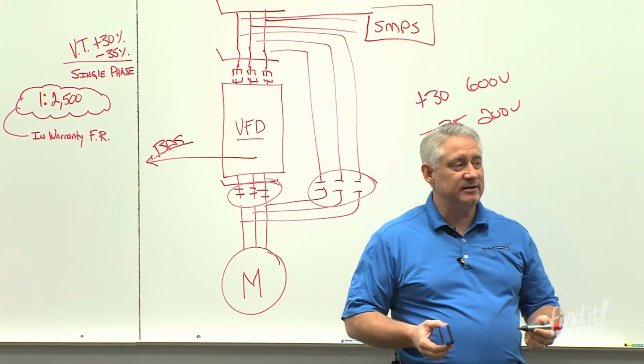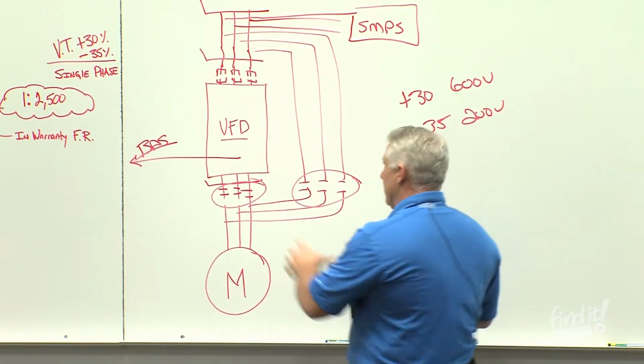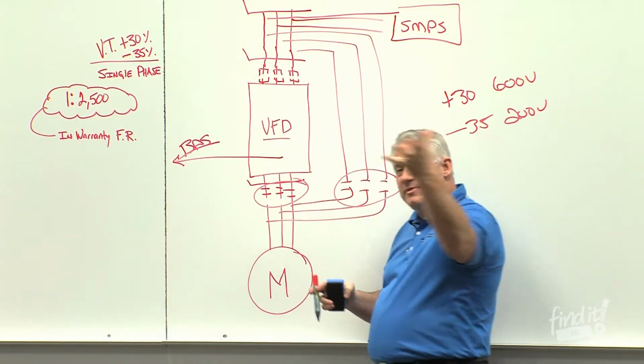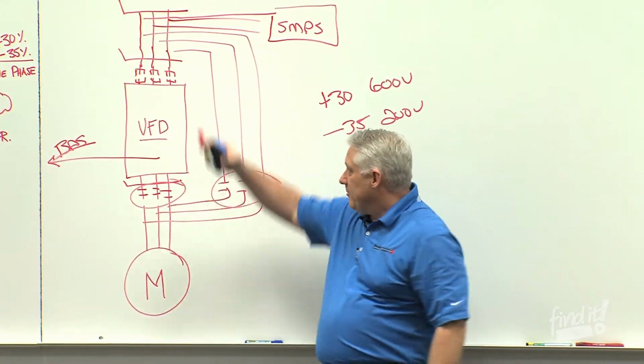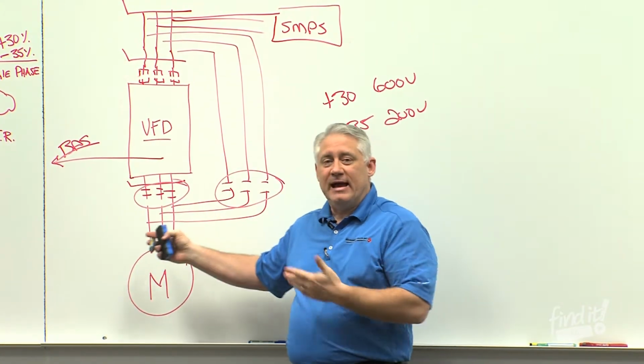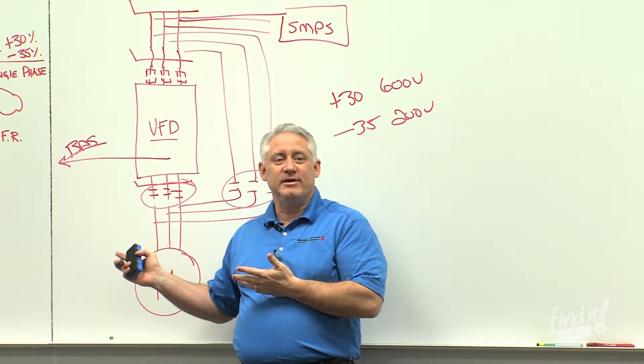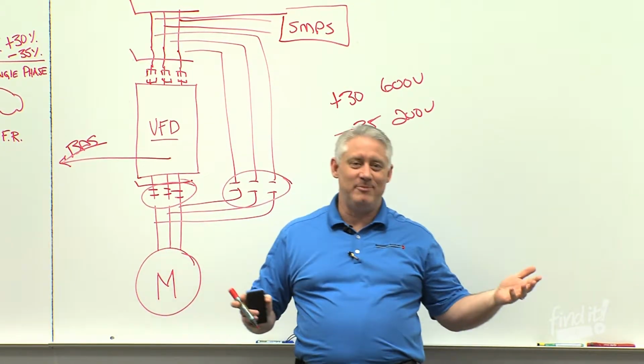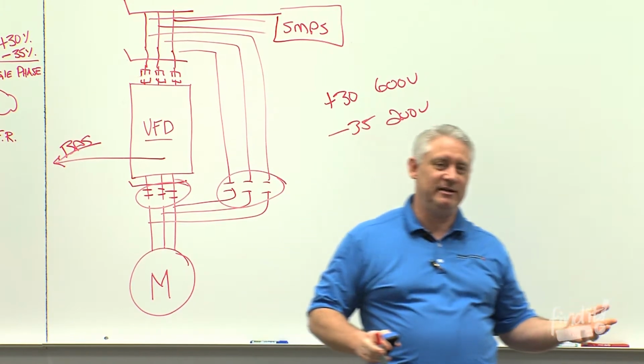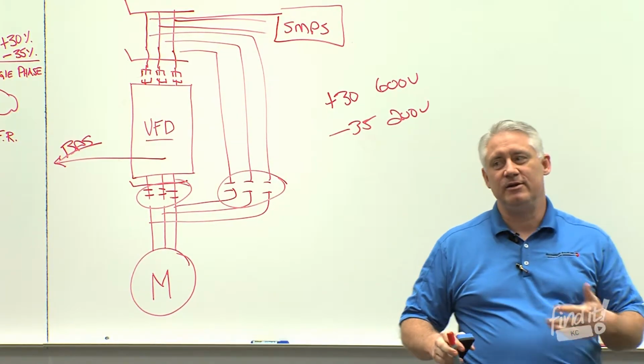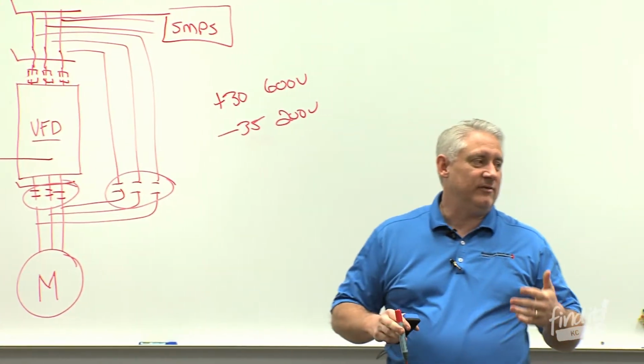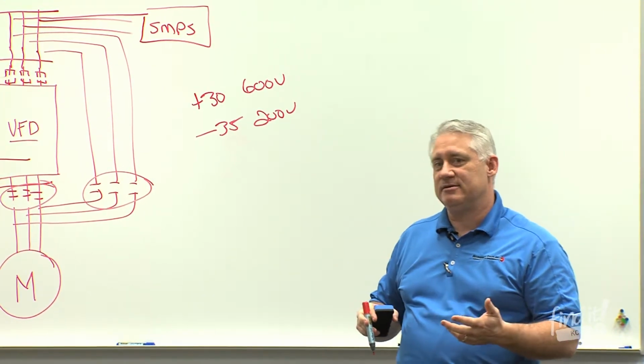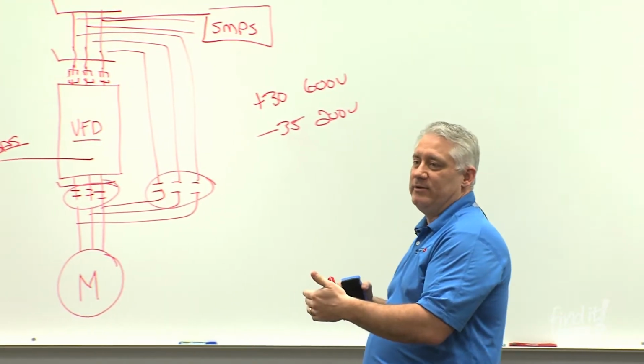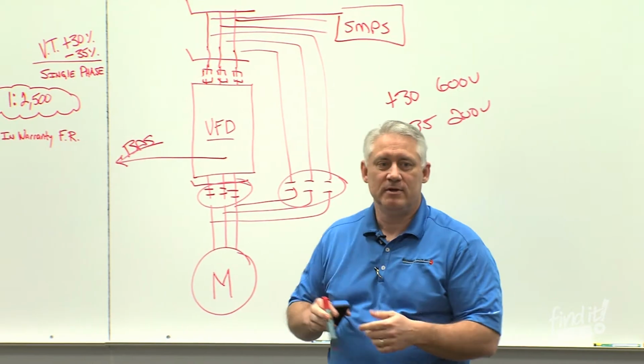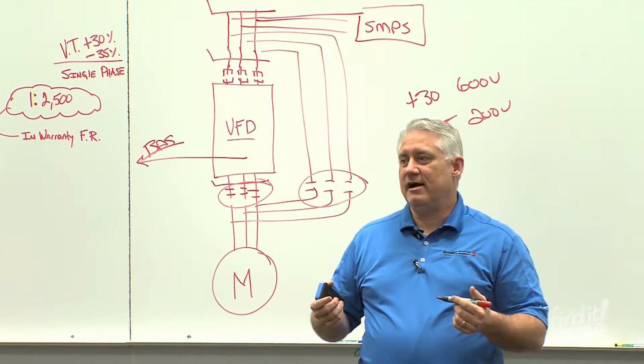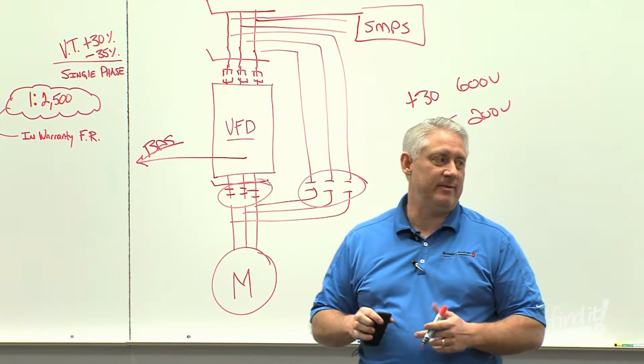Why that's important is if you have a drive failure and the drive needs to be removed from the system, we can still operate in bypass, and we now can also communicate to your building automation system, let you know that you're in bypass, that you're no longer saving energy. It's running full speed. You don't have variable flow. So we have a lot of capabilities built into the systems that are far beyond what they were 10 or 15 years ago. So that's a drive and a bypass in the history of bypass.